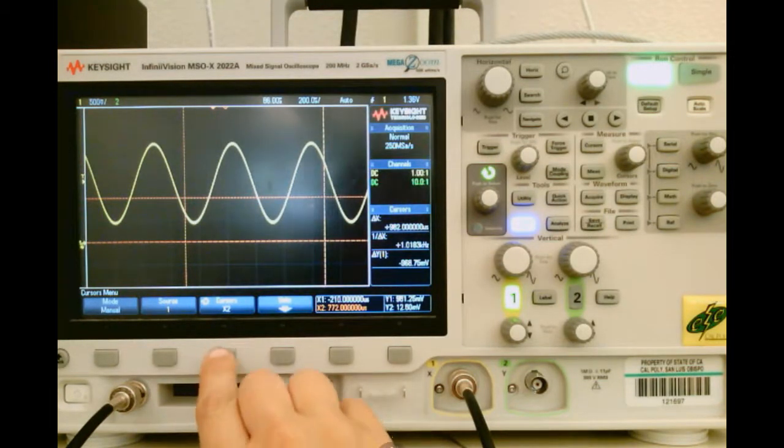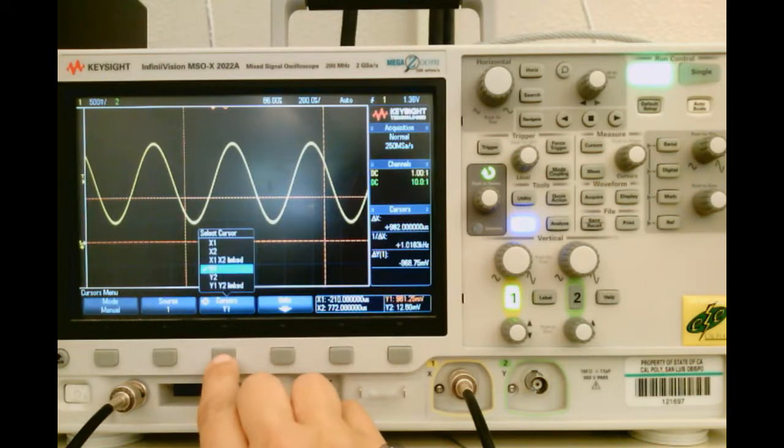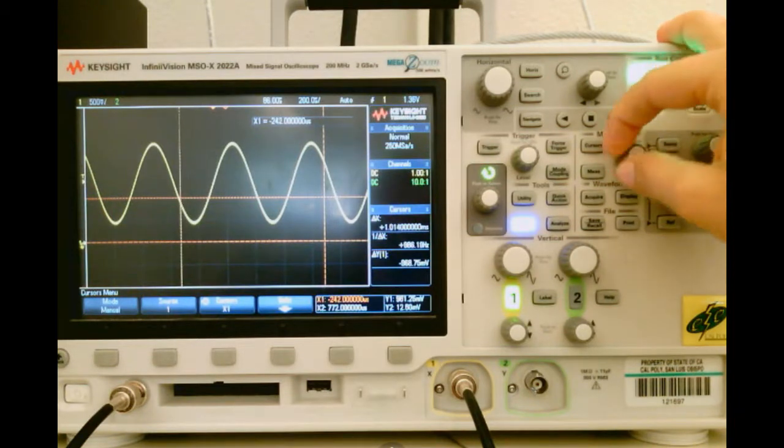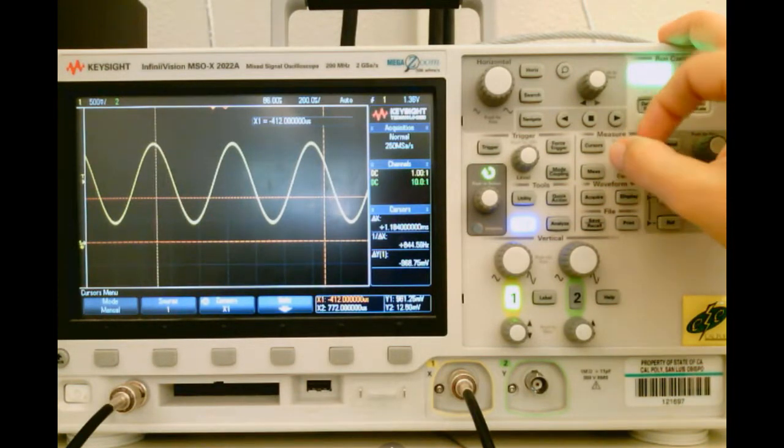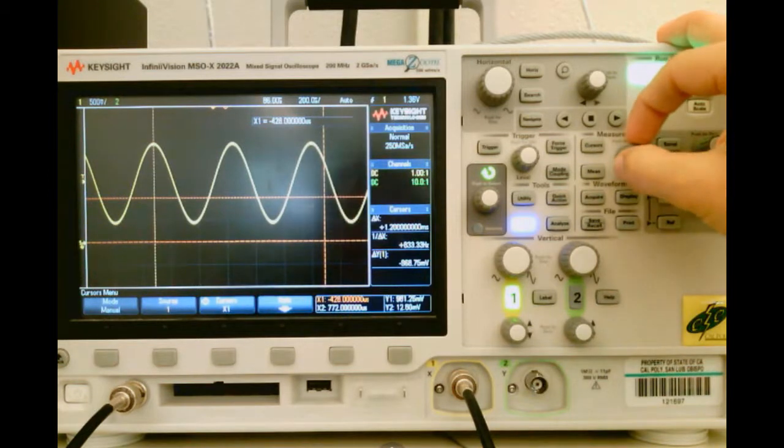So let's go ahead and move the first cursor, which you can change the cursors you're using. Let's pick X1. Now use the Cursors knob to move that cursor to the peak of your waveform. So that looks like it's about at the peak.